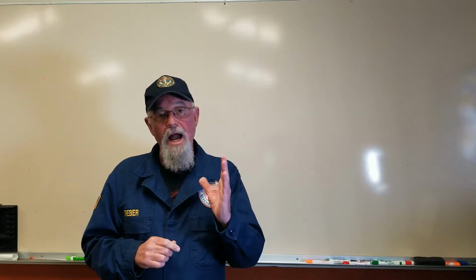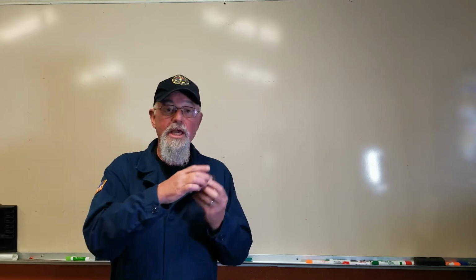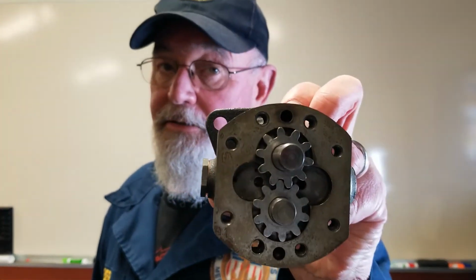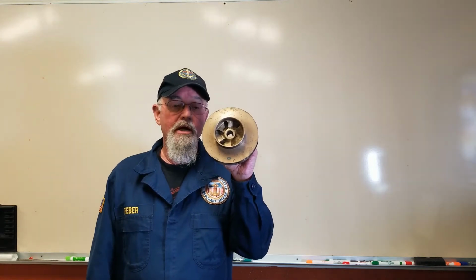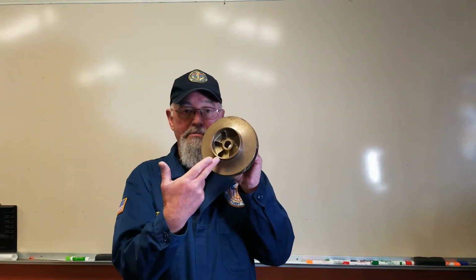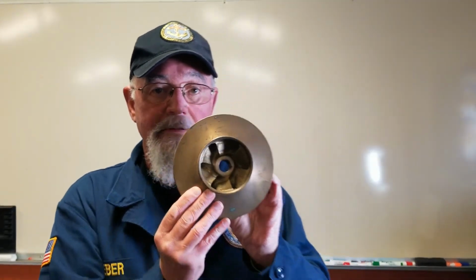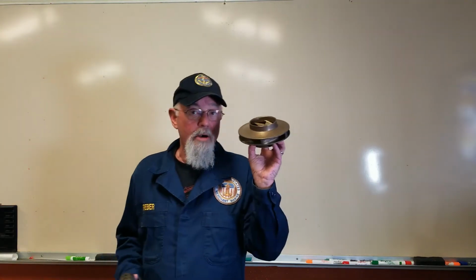You're also placing in operation 2 different pumps. One of them is the circulating oil pump, a positive displacement rotary gear pump. That's going to circulate lube oil from the sump back to the sump through the lube oil heat exchanger. You're also energizing a circulating jacket water pump, which is a non-positive displacement centrifugal pump. It has an impeller. A non-positive displacement pump is used for water because water is a non-viscous liquid, and since oil is a viscous liquid, we want to use a positive displacement rotary gear pump.